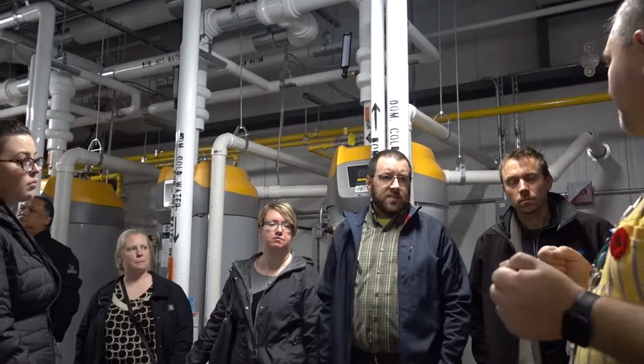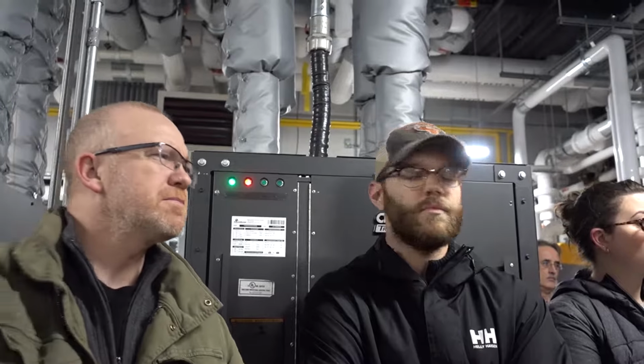What sort of COPs are you getting on the compressors from your heat pumps? Sorry, what are those? Coefficient of performance. We're getting about 4.3 on the cooling and 3.5 I think on the heating side. Peak conditions. I'll let him tell you if that's good or not. That sounds good.